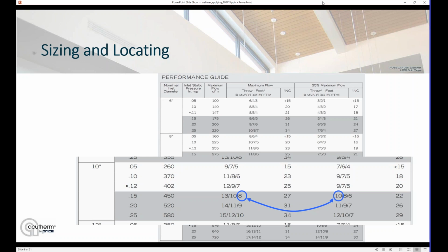To put into example what we were just talking about, I've pulled a performance chart here on the screen from our Model TF diffuser, just looking at a 10-inch diffuser there at a 0.15-inch static pressure. And what I'm looking at is under the maximum flow or the 100% flow condition, the 150 feet per minute throw distance is 8 feet.